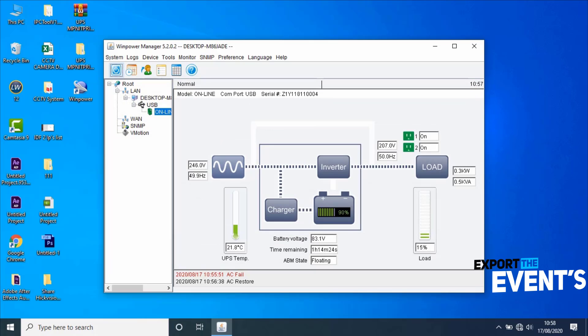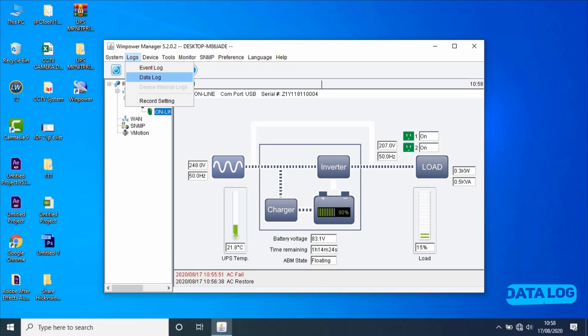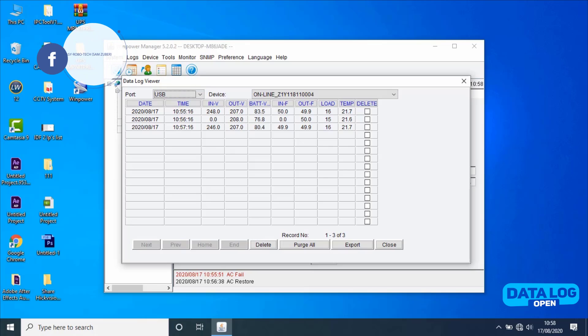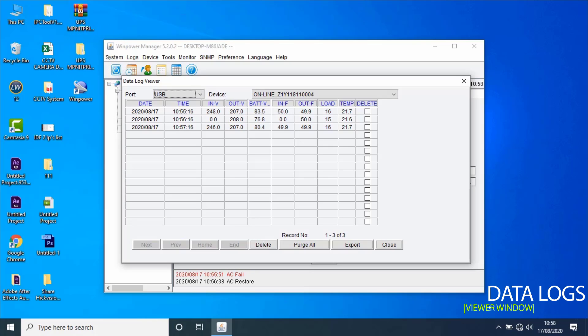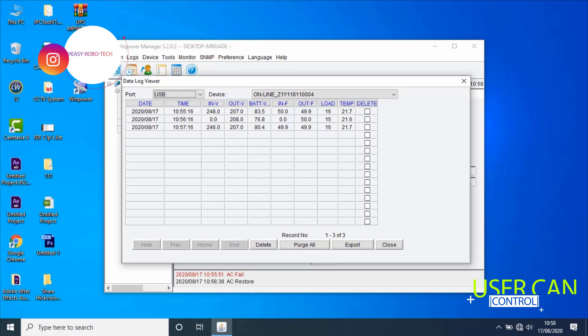Let's close this window and go back to Logs, then open Data Log. The data log viewer window will open. The user can see detailed logs for the UPS, such as input voltage, output voltage, battery voltage, input frequency, output frequency, output load, and internal temperature.